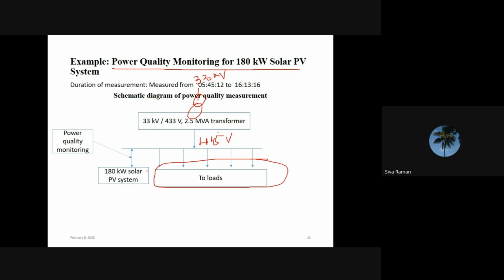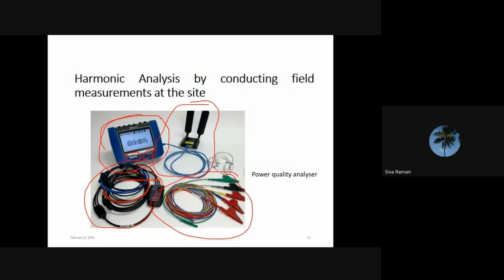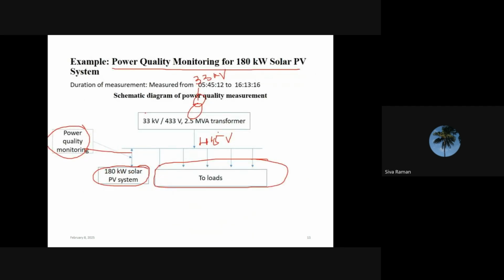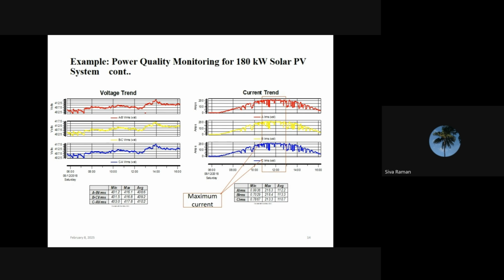It has the internal load also. So the total aggregated solar PV capacity is 180 kilowatts. The power quality measurement is performed at this location. This is the Dranetz power quality analyzer we have used for the measurement. This is the voltage and current value from the power quality measurement. The left one is the voltage and the right one is the current.